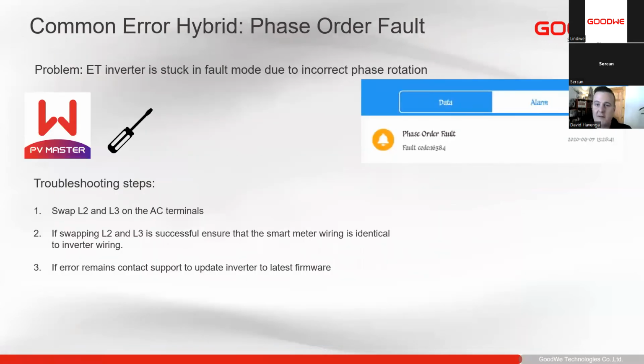So the next error we have is phase order fault. This is for our 3-phase inverters. They are sensitive to the phase order or direction, so they always want to make sure we have a right-hand rotation of the phases. For most homes, it doesn't really make a difference. Most people don't even use phase rotation in their homes because they don't have 3-phase motors running. Only with a 3-phase motor does phase rotation really become a requirement. So the inverter just makes sure that the phase rotation is correct.